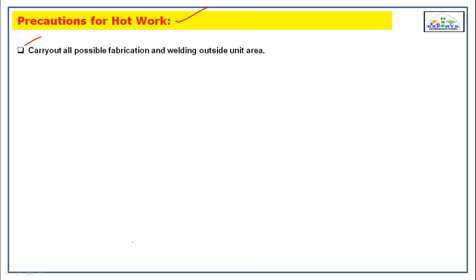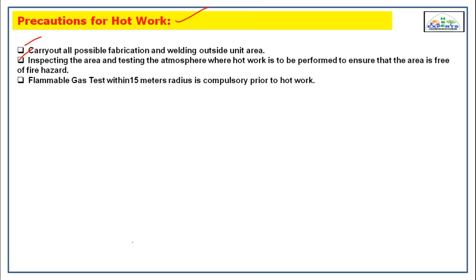Precautions for hot work: carry out all possible fabrication and welding outside the unit area. Inspect the area and test the atmosphere where hot work is to be performed to ensure the area is free from fire hazard. A flammable gas test within a 15 meter radius is compulsory prior to hot work. Clear combustible materials and heavy oil deposits within an 8 meter radius. A valid hot work permit must be obtained. Cover and seal sewers, drains, vents, or any other gas escaping points within a 50 meter radius.